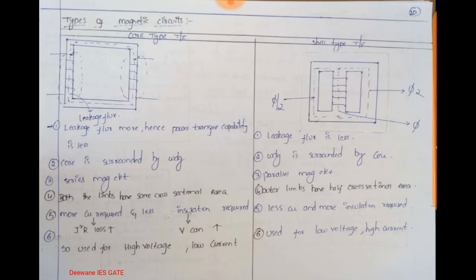Insulation level is directly proportional to voltage. If voltage rating increases, we must increase insulation level. Since insulation required in core type transformer is less, we can use it for high voltage rating. But copper requirement is more — if more copper is used, I-squared-R losses increase. So core type winding is used for low current and high voltage applications.